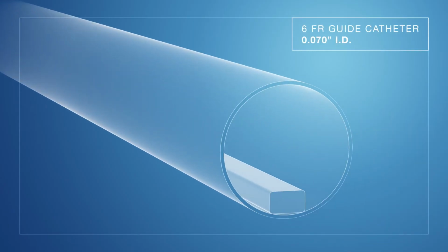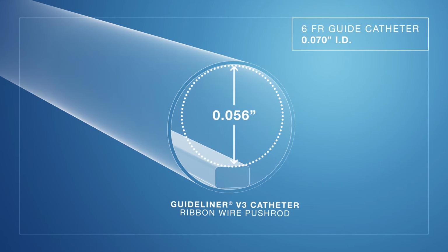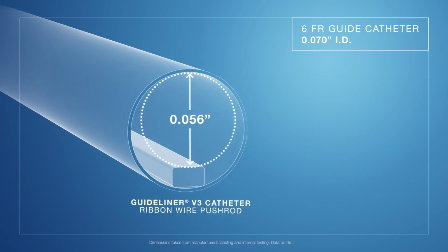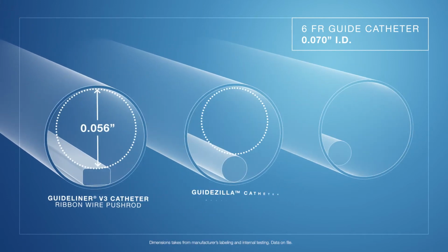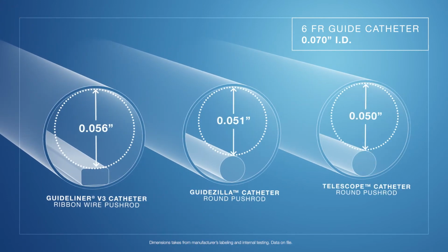It allows you to deliver more gear, larger gear, through your guide catheter, through the guide extension, and to the target lesion. We're 56 thousandths from the moment you enter the guide catheter to the moment you exit the distal tip. When you look at some of our competitors, they chose to do a round push rod. They're giving up 5 to 6 thousandths in that guide catheter. The design differences can seem small. In the end, that makes a huge difference on whether or not your case is successful. 5 or 6 thousandths in effective ID, that's a big number.